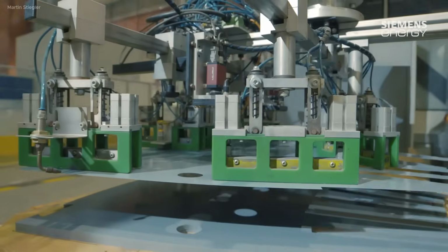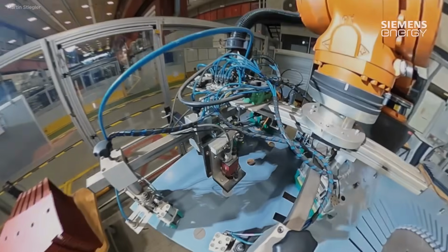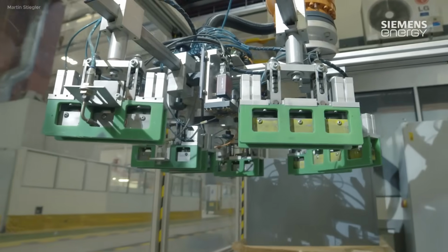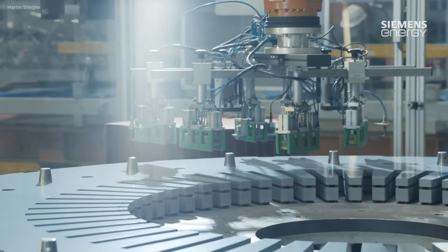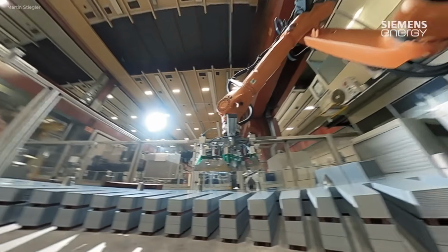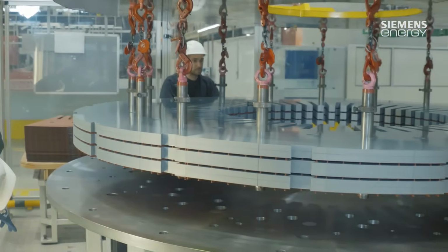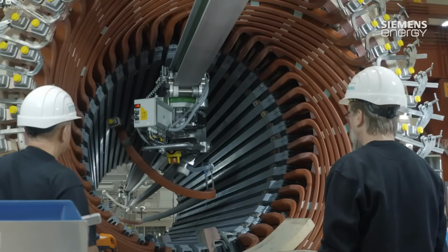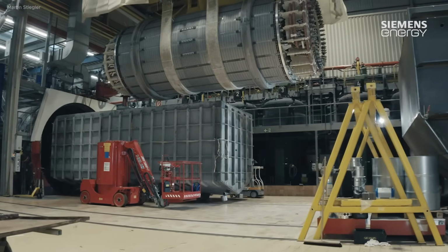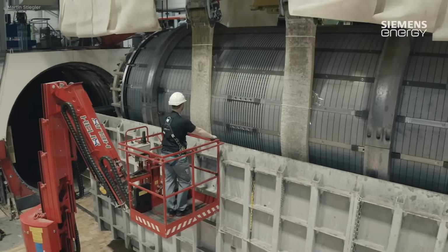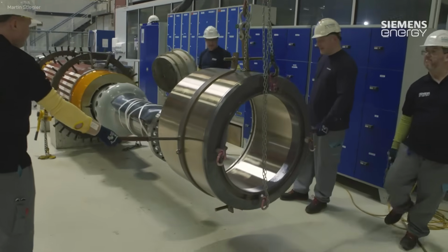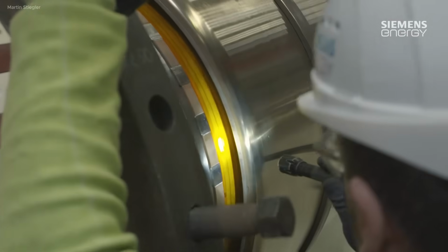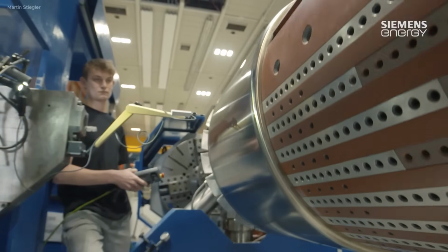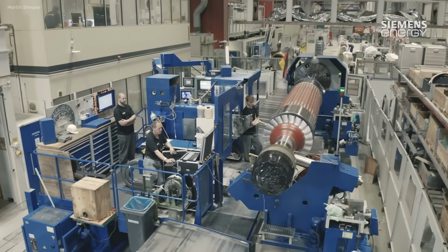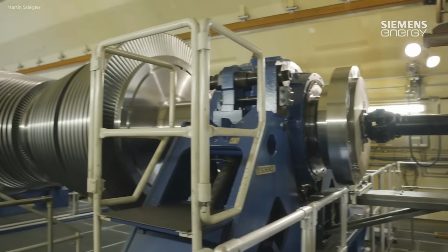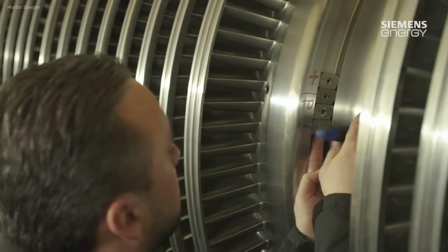The rotor shaft is precision machined in several steps, followed by a quality inspection. Its winding cap is thermally expanded and mounted. A final roundness and dimensional check is performed on a lathe. The stator and rotor are then assembled in a process called the marriage. Before shipment, the complete generator undergoes extensive testing in Siemens Energy's high-tech control center. This ensures reliable operation under real conditions and secures long-term performance in power plants or grid stabilization systems.